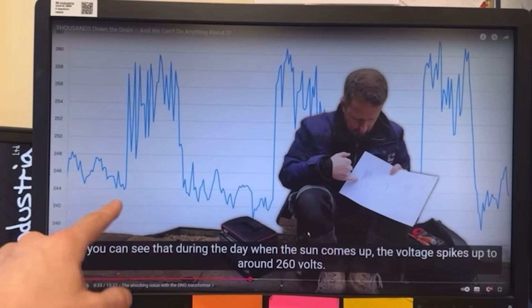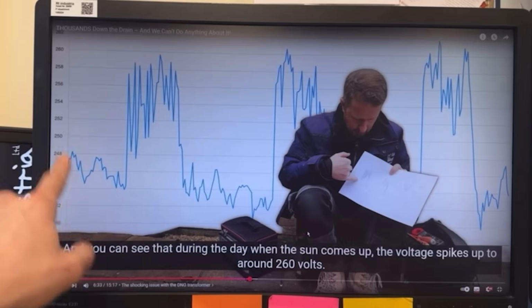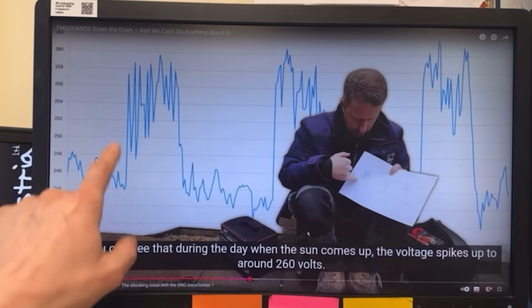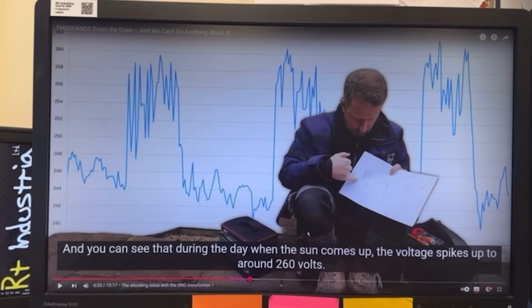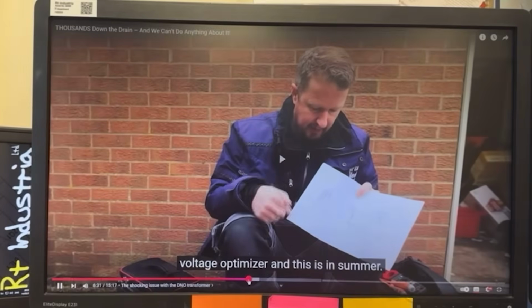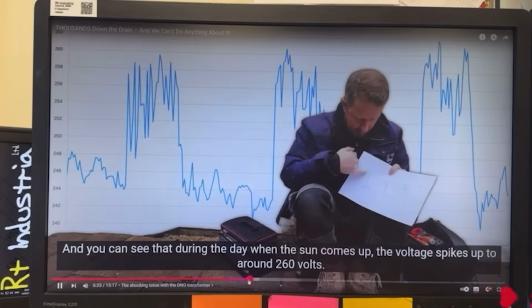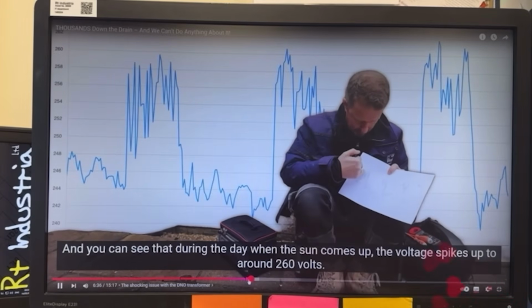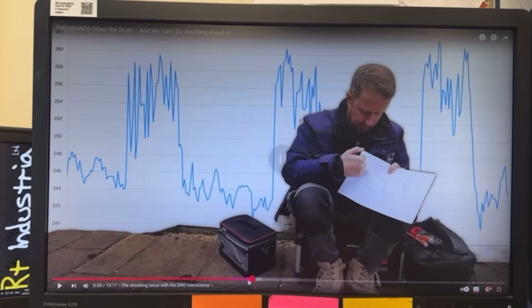I'm guessing they're not putting load on at night at this time of year because this isn't going down enough, because that's the sun and that's just a normal load of the battery charge at night, I assume. And this is in summer, and you can see that during the day when the sun comes up, the voltage spikes up to around 260 volts. Which must mean that additional solar on the grid in the local area, or maybe big solar farms nearby, are causing problems, because as the sun comes up there's more energy available and it's got to be distributed around the grid.